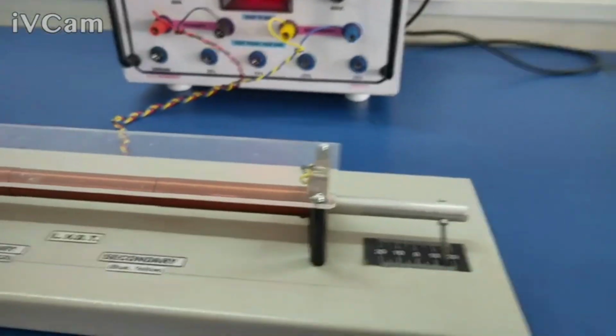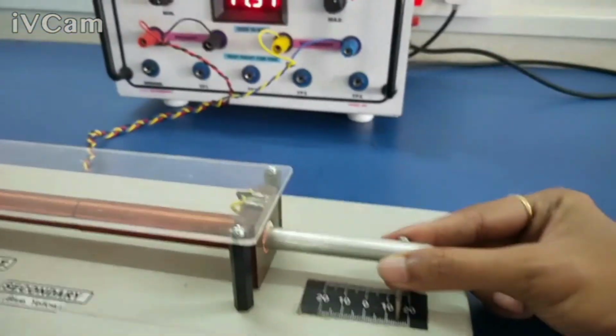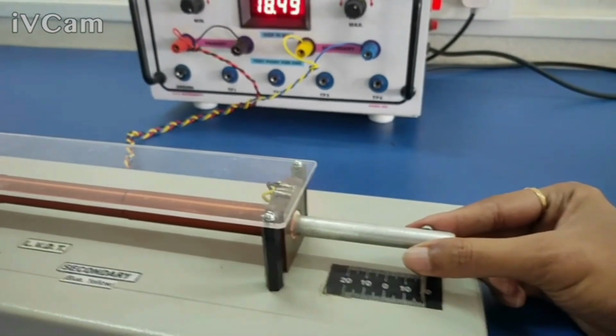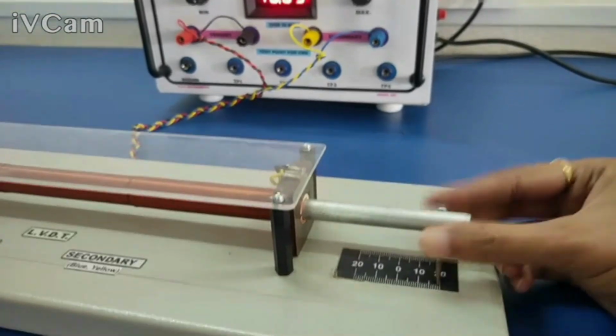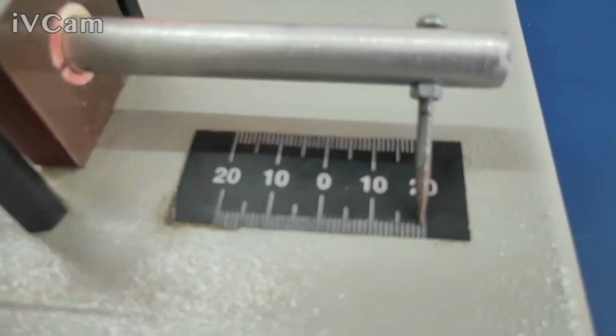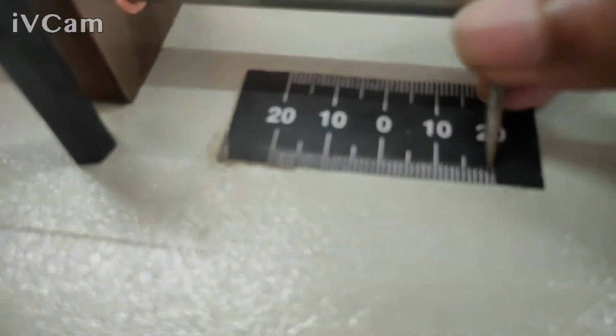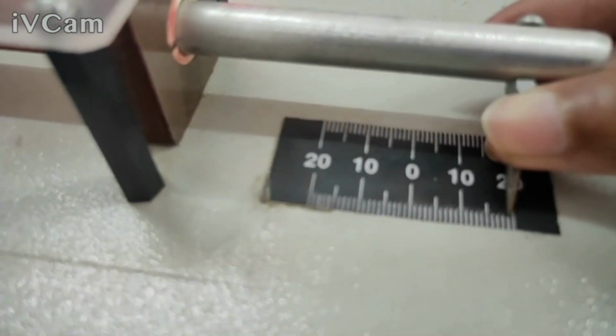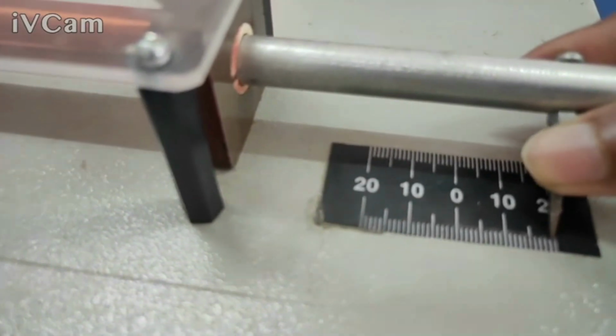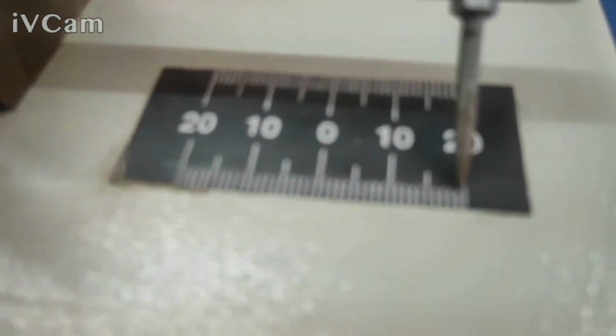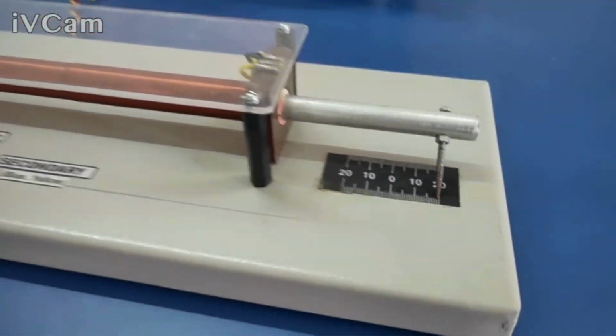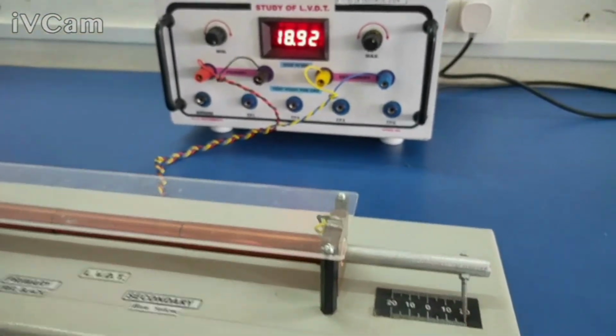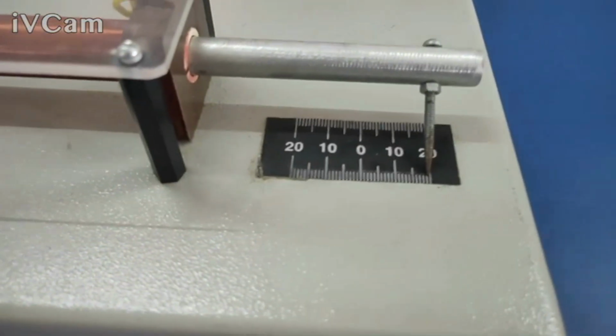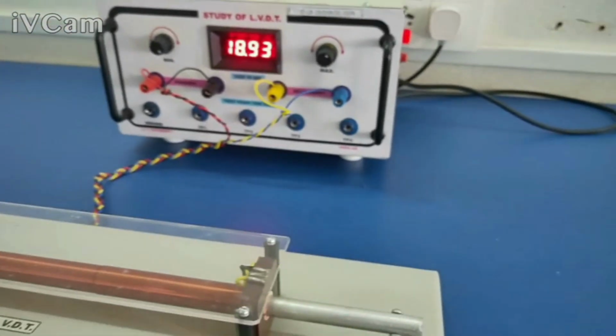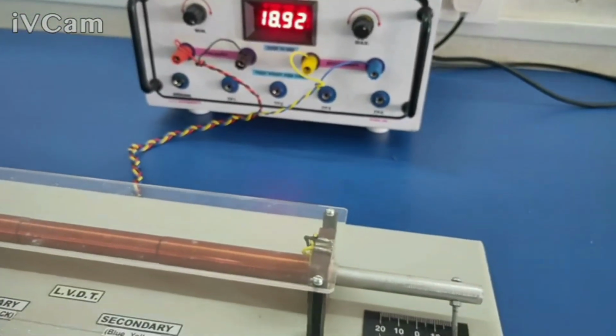Okay, so let us suppose I make a displacement of the core physically to 19. Okay, so let us see here, I am positioning slightly less than 20. So one less than 20, that is 19 mm, is the positive displacement here, and what you find on the DPM is 18.92. So we are going to take the readings as the actual displacement in millimeters on the scale and the value that is being read by the digital panel meter. Okay, that's how we are going to take the readings.